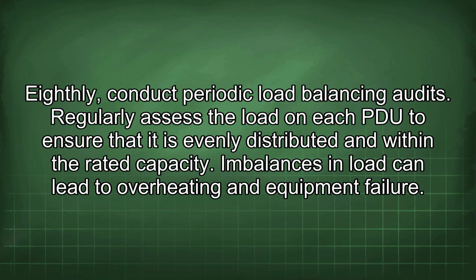Eighthly, conduct periodic load balancing audits. Regularly assess the load on each PDU to ensure that it is evenly distributed and within the rated capacity. Imbalances in load can lead to overheating and equipment failure.